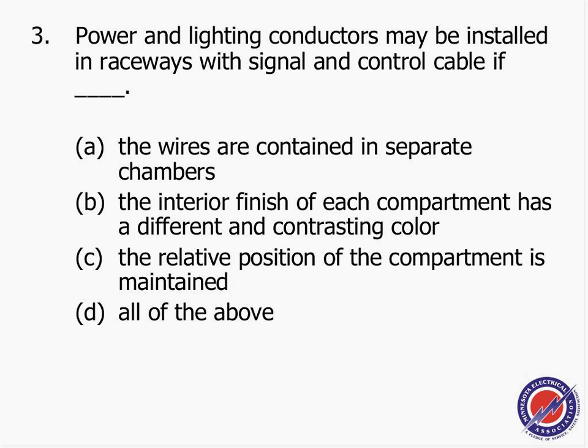B, power line conductors may be installed in raceways with signal and control cables. Number 3, and our answer for number 3 is D. I want to highlight this one, guys. It says wireways are contained in a separate containment. Separate is the key point. The interior of each compartment has a different contrast color, and the relative position of the compartments is maintained. Can I put low voltage and high voltage in the same wireways or raceways? No problem, as long as you maintain complete separation and identification of the two chambers.